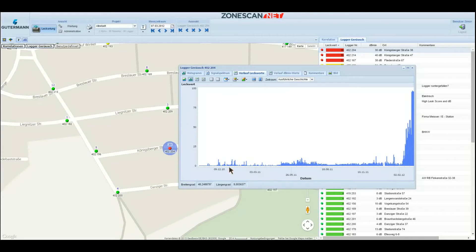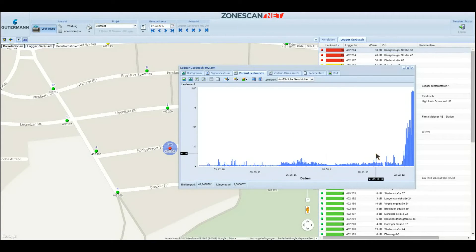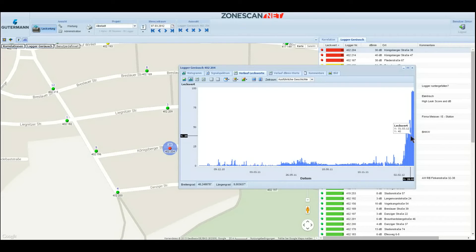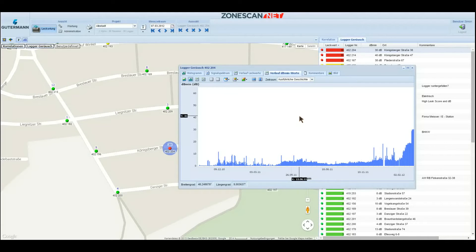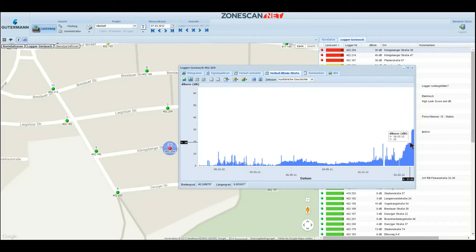In this situation here, you can see from this historical chart of leak values of this logger, starting right back from the 23rd of October 2010, that this logger has been relatively quiet for a long time until a leak started appearing, slowly developing and making more noise over the period of a few weeks, and finally reaching its maximum size with a leak value of close to 100, a strong indication for the existence of a leak. The same principle applies to the minimum decibel values, which are always at a relatively low level and start rising slowly and continuously towards March 2012, to reach the maximum level of 30 decibels.